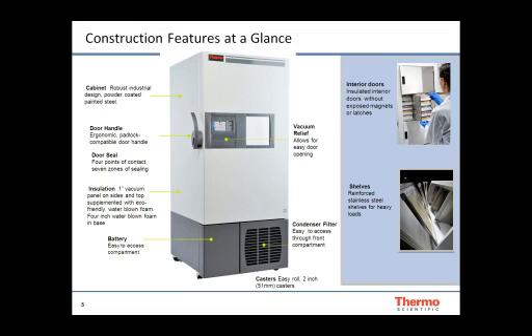Vacuum relief port, we have a heated vacuum relief port. We do such a good job of sealing the unit that if you don't have a vacuum relief port, I think as Warren mentioned, you can't get in and out of the unit. So that's critical. Interior doors, our doors are insulated. We use a rare earth magnet for very good sealing, and they give very, very good protection to the samples. And then finally, stainless steel shelves that are reinforced to be able to hold the loads that people are putting in and out of an ultra-low.